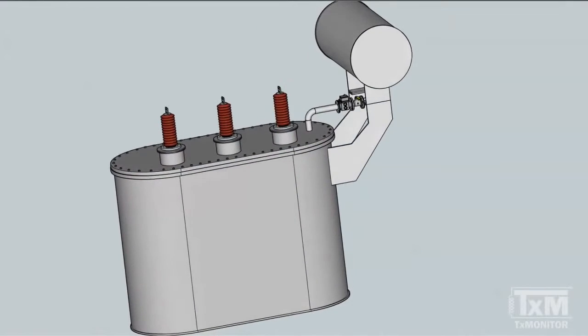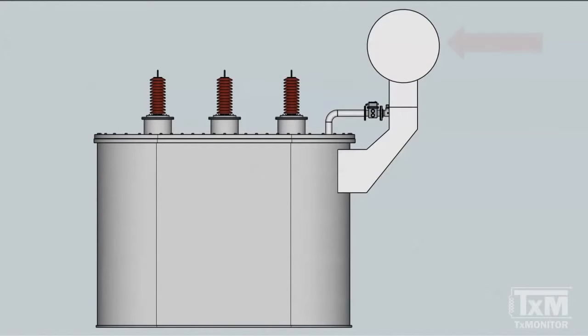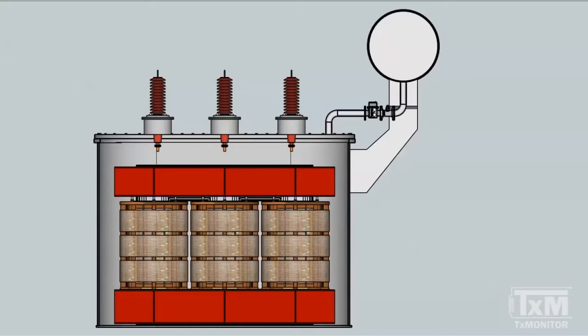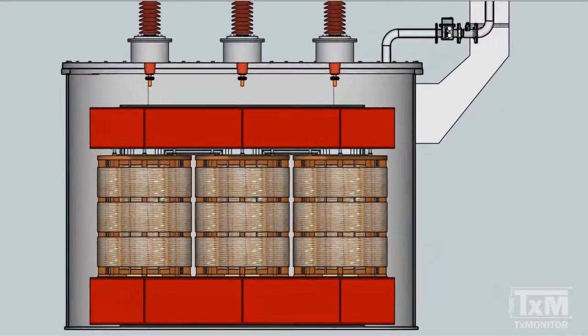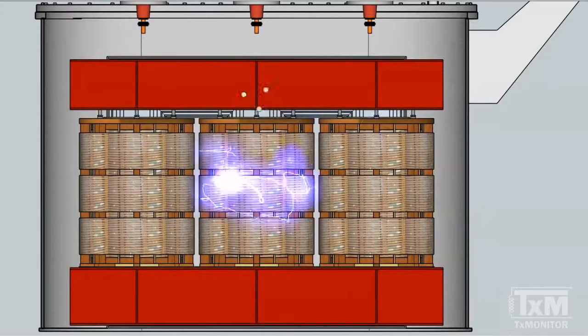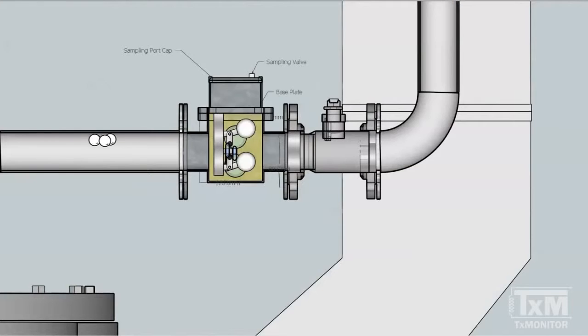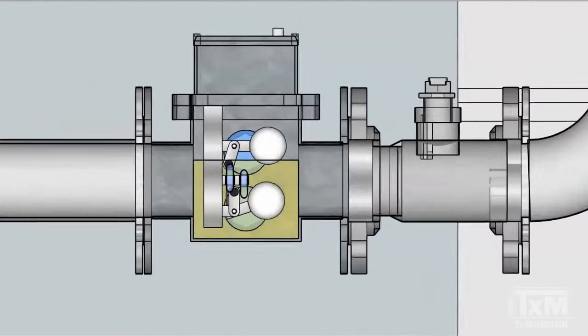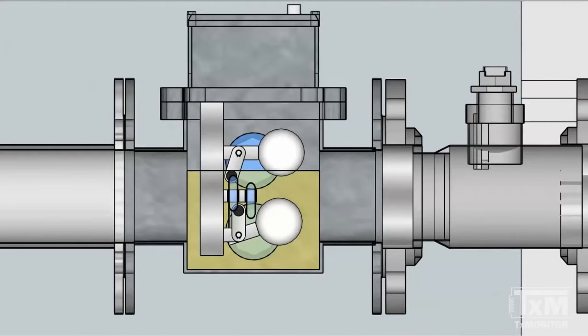On transformers where the liquid preservation system design uses a conservator tank, a Buchholz relay is commonly fitted to provide protective functions and accumulate gases released from the transformer. When, for some reason, gases are not dissolved in the insulating liquid, they evolve in the form of bubbles. These bubbles tend to rise inside the unit and find their way to the conservator through the pipe connecting the main transformer and the conservator tanks.